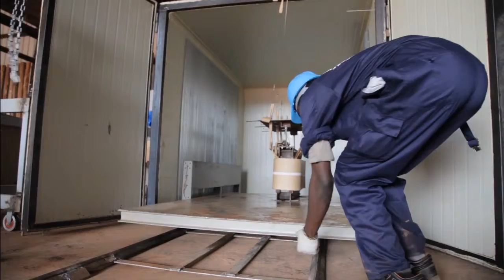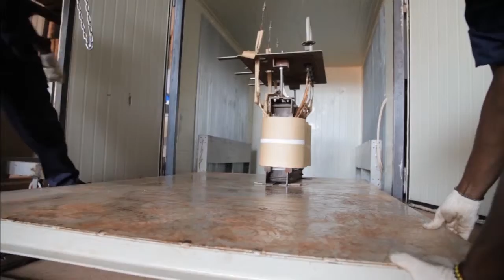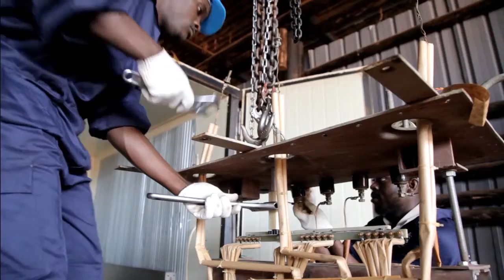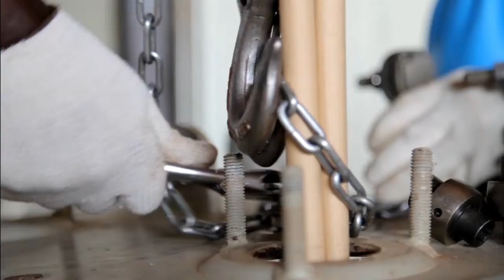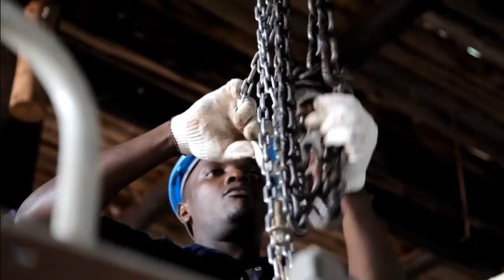Check the ratios first. We remove the transformer from the tank. We wait until it leaks down. Then we open the burnt coils. We calculate the ratios, voltages. We first check the conductivity of the wire, the type of the oil, and then we consider insulation.